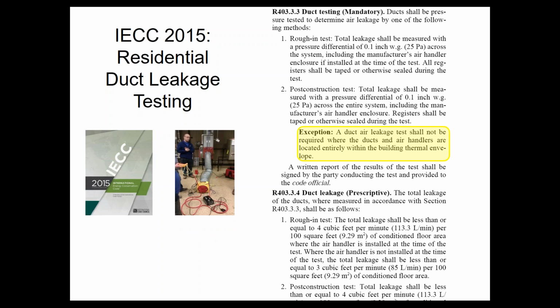But as soon as you put a 5-foot run up into the attic or through the crawl space or an exterior wall, then immediately the duct testing requirement comes in. You have to not only seal the duct and test it, but get it down to a certain leakage level. That level is 4 CFM per 100 square foot of home if you have your air handler installed, your furnace installed. If you do not have a furnace installed yet, then you'd have to have 3 CFM per 100 square foot of home. So to make life easy on myself, if I had a 2,000 square foot home, I would be allowed 80 CFM maximum leakage if my air handler's in.